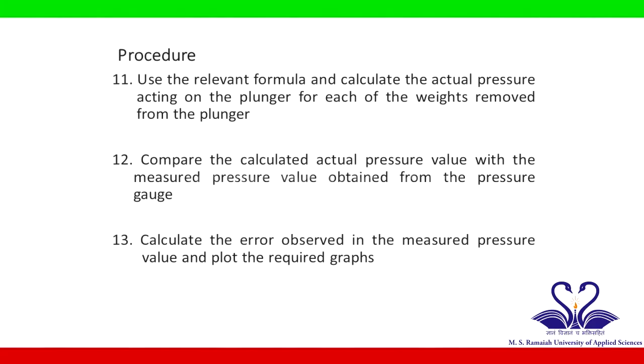Now, using the values of the weights and area of the plunger, calculate the actual pressure acting on the system for each of the weights that are removed from the plunger. Compare the calculated actual pressure and the measured pressure as obtained from the pressure gauge. Calculate the error between the actual pressure and measured pressure and plot the required graphs.